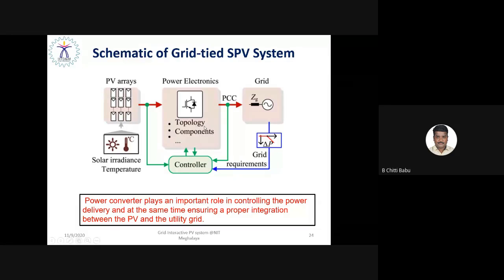While integrating the solar PV system with the utility grid, the power electronics converter with a suitable controller has to satisfy the grid connection requirements. These grid connection requirements include active and reactive power control. Decoupled control of active and reactive power is very essential to control the frequency as well as the voltage. Moreover, it has to have an excellent transient response and grid synchronization, and provide inertia to the system so that it can damp out any oscillation, and provide reactive power support as well, right? So the power converter with a suitable controller plays an important role in controlling the power delivery, and at the same time ensuring proper integration between the PV and the utility grid.